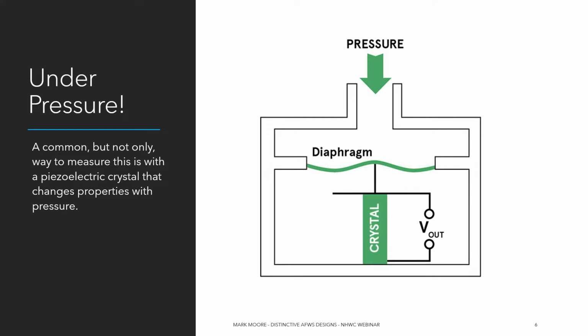So how do they work? Well, they're under pressure. A common, but certainly not the only way you can measure it, is with something called a piezoelectric crystal, which is not going to be on any exam, don't worry. But a piezoelectric crystal is basically a little sensor in these pressure transducers that has a change of its electrical properties when pressure is placed upon it. So I'm not sure if my mouse is completely visible here, but you've got the pressure pushing down on that diaphragm of that PT, and when it pushes on the diaphragm, it pushes on the actual crystal, which has that electrical change and can be monitored and related to water level.